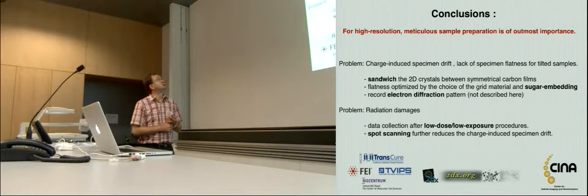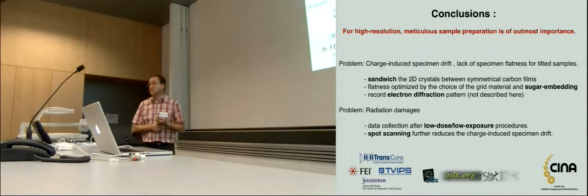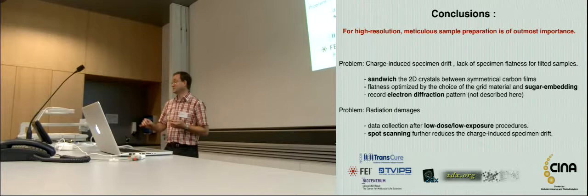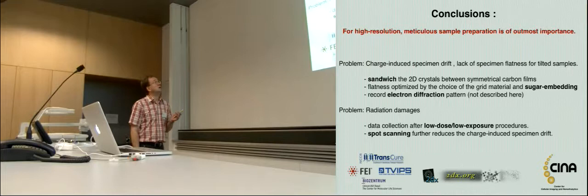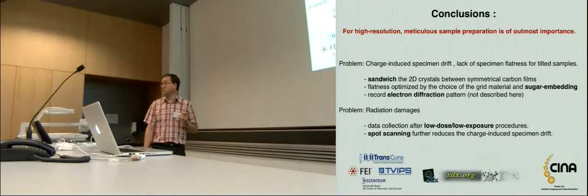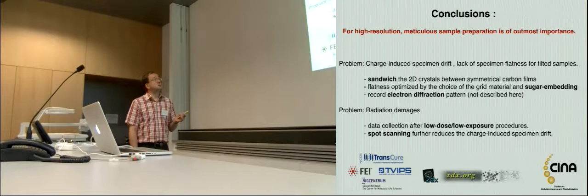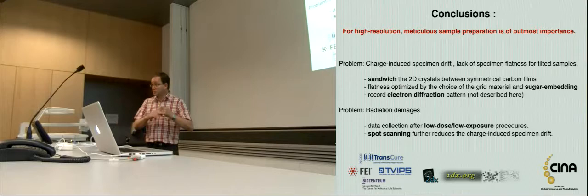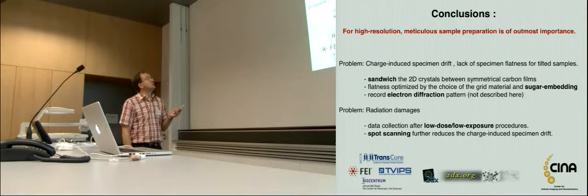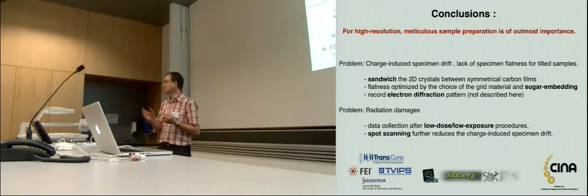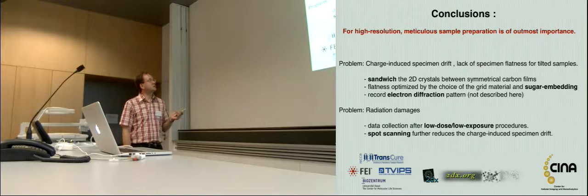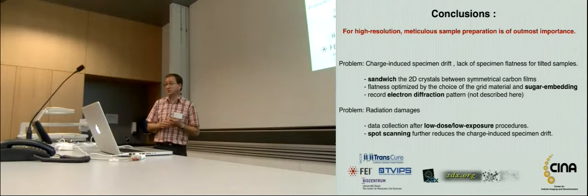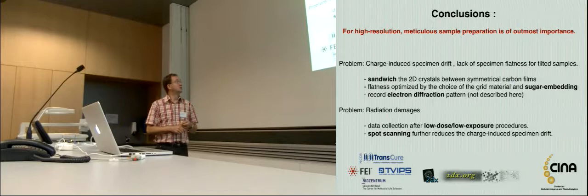I would say that for high resolution, you need to be meticulous. That the sample preparation is of extreme importance. Of course, 2D crystals are the first bottleneck. You first get 2D crystals. But then there is a lot to do. And the charge-induced specimen drift and lack of flatness can be solved, plus minus, by the sandwich method, by choosing good grid materials like this molybdenum, and the sugar embedding also helps to get the flat carbon. And you can in addition, you could also do electron diffraction, but this is not described here and will not be used in this workshop. And for the radiation damage, it is very clear to use low dose, low exposure. And furthermore, you can use spot scanning to reduce the charge-induced drift. Now I am finished with the talk. And I want to thank the sponsors and our institution for letting me do this. Thank you. If you have questions.